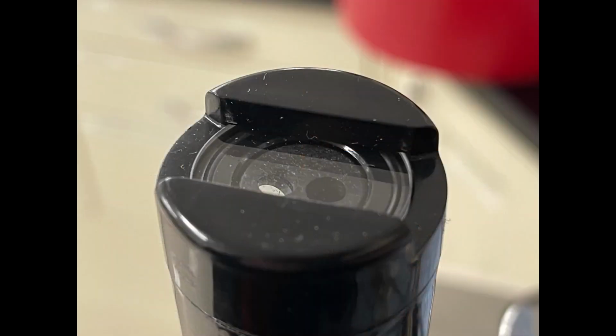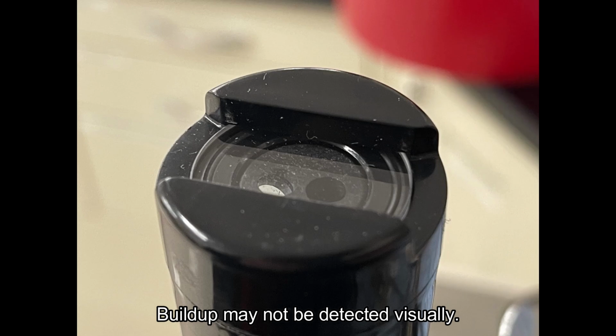I also want to mention too that even if the LD2 looks clean, it may still be worth giving it a cleaning because it might have some microscopic buildup that's hard to see with the naked eye that could still affect the reading. So anytime you get a reading that is off from what is expected, don't recalibrate. Try cleaning first and then check to see if that helps with the issue.